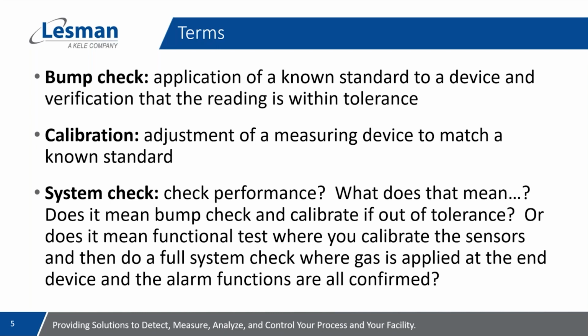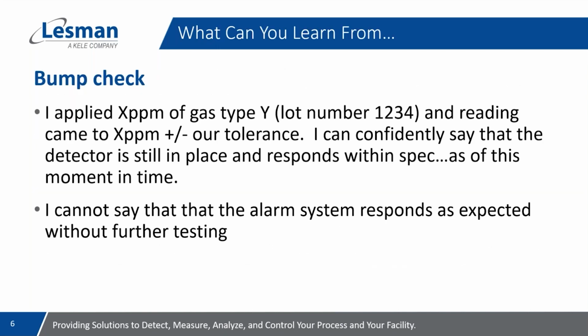The other type of test is a system check, or performance check. But this gets very tricky unless you have a clearly defined scope of work. We're going to dig into this a little bit later on. So what can and can't you learn from each of these maintenance activities? A bump check confirms that the sensor still responds to gas within performance expectations, within limits. When you put gas on the detector, do you measure the time it takes to reach your target concentration? Is that part of your performance expectation?